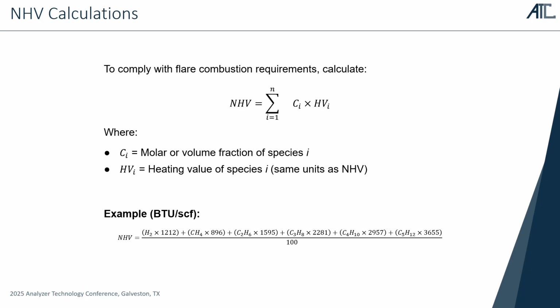And then the NHV was also calculated. The NHV is calculated based on the molar fraction of each species that contributes to the heating value, times the heating value of the species, and that gives the total BTU per scf for that flare. This is why, with something like a mass spectrometer, you're able to speciate very accurately, so you can calculate the NHV without requiring any additional calorimeters or anything like that.